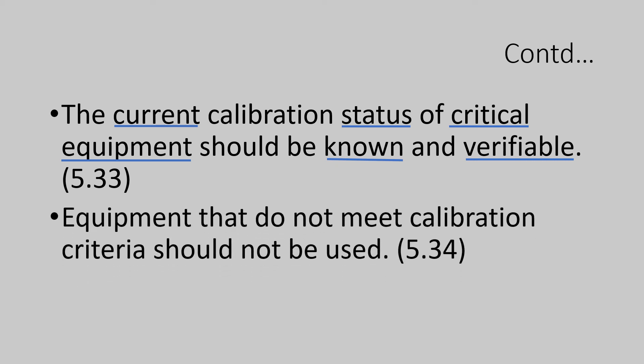Let us see what section 5.34 says: equipment that does not meet calibration criteria should not be used. This can be achieved by displaying a status board indicating that the particular equipment should not be used in manufacturing from the date on which it broke down. The peripheral issues to address are: when was it last failed, and what is the impact of this failure during that period? There should be a provision to investigate the batches manufactured before the breakdown for any adverse impact. In your SOP, there should be a provision to investigate for all such breakdowns.